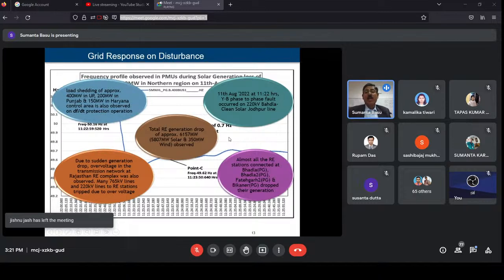Finally, all these disturbances led to load shedding of approximately 400 megawatt in UP, 200 megawatt in Punjab, and 150 megawatt in Haryana control area, on the df/dt protections. The rate of change of frequency was very high under this event, and all those regions had to do mandatory load shedding. I will show you the background, and why it affected the other regions.